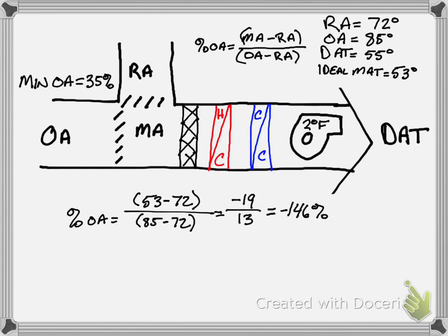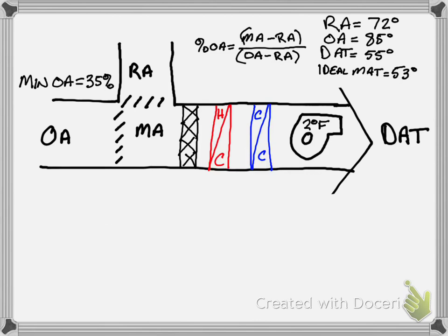And so what we have to do is we have to solve to see what our mixed air temperature is actually going to be. In this scenario we are using the same equation, but we're doing it in a different way. Now we know that our outside air percentage is 35%, because it is our minimum. And we do not know our mixed air temperature, so we'll represent that as X.